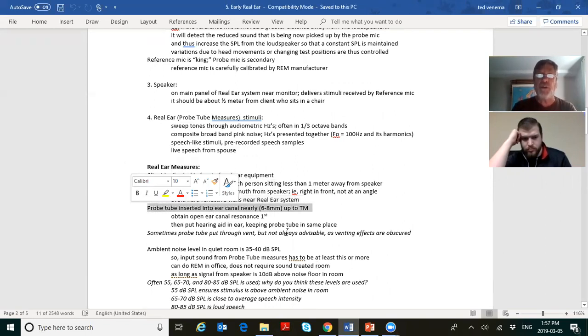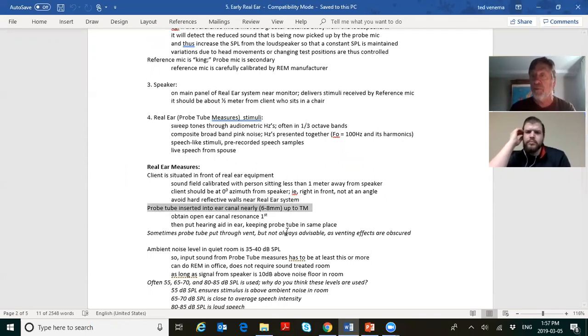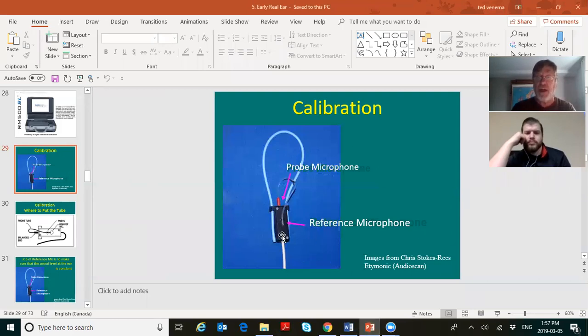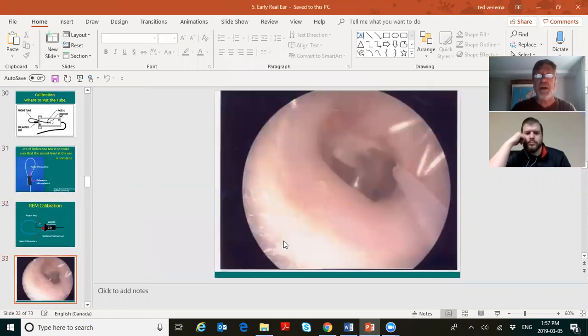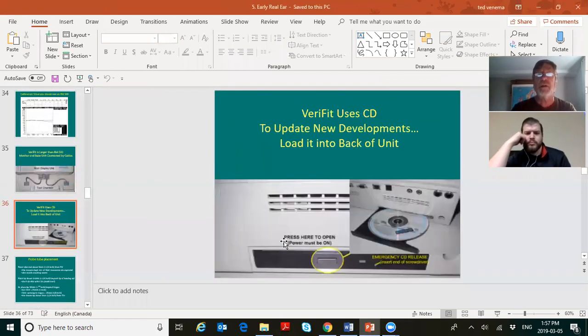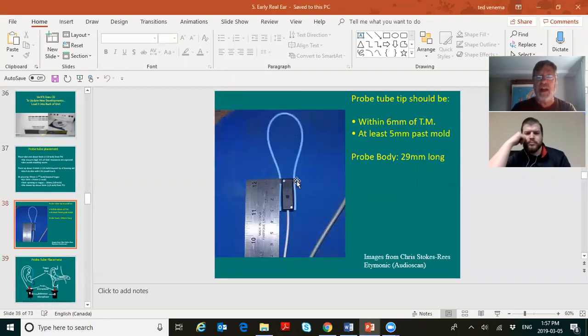And how far do you insert the tube? Well, we all know that the end of the tube should be about 1/4 of an inch from the eardrum. That's why the little ring, and why the black box is usually 29 to 30 millimeters in length. The black box has its purpose being exactly that length, so that when you lay the tube along the whole black box, here's that. See the length of the box, and the tube would be laid over the top of the box. If the tip of the tube is here, you'd want to place the ring right here.